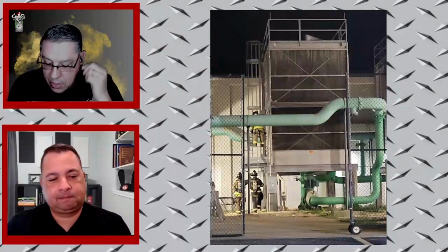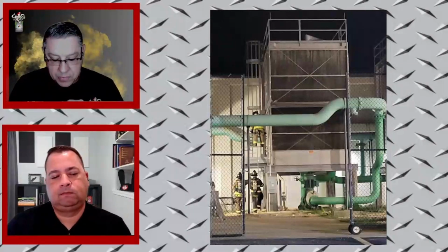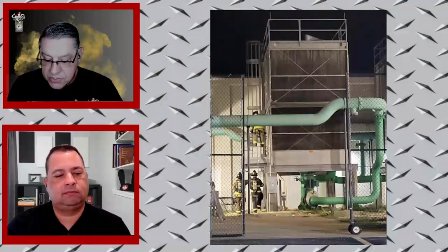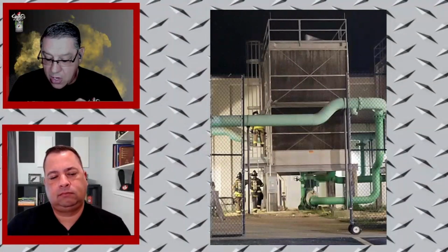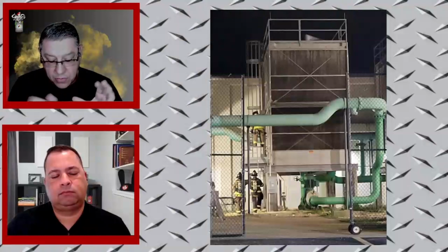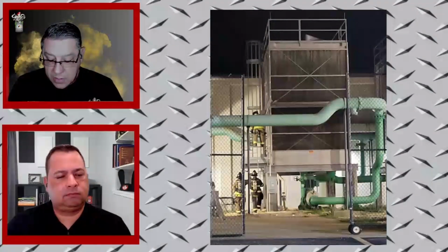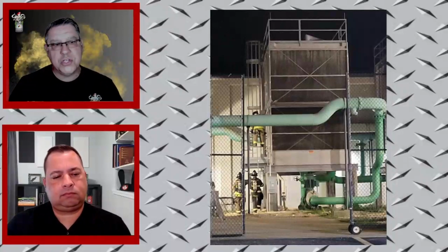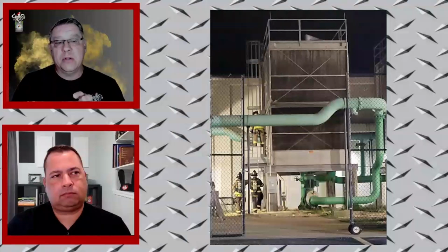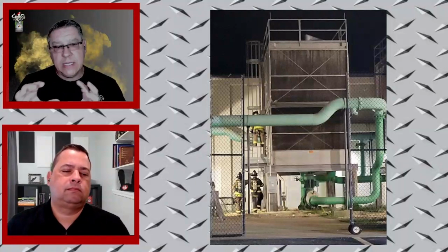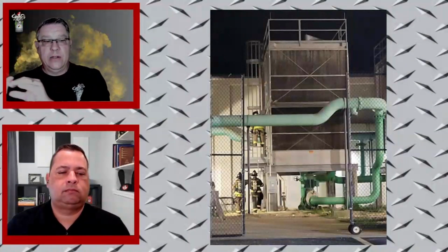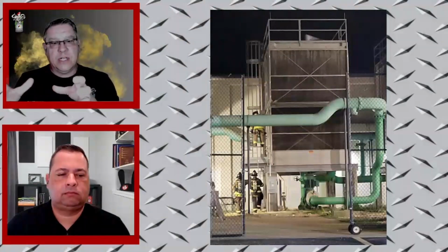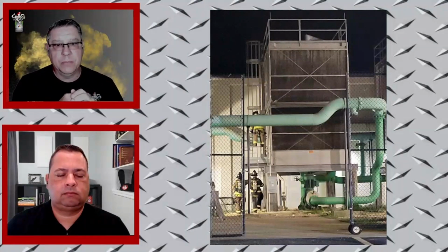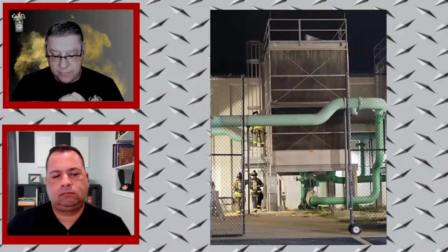The crews entered with a multi-gas meter, PID, and a TIC to investigate further. Their CO readings were around 115 parts per million on the AB side of the chiller. As they went around the chillers, the CO readings dropped down to 20-40 parts per million. So they were able to use their meter during their 360 to isolate the general area where this was coming from.